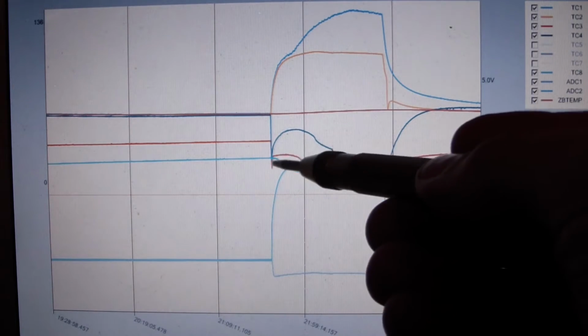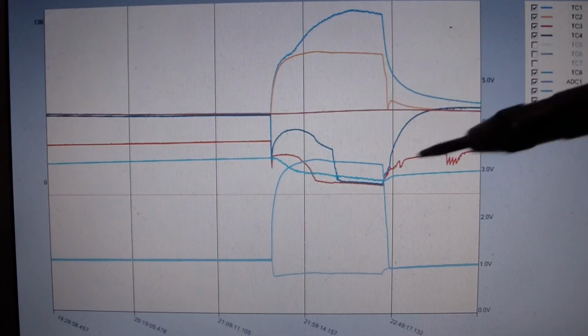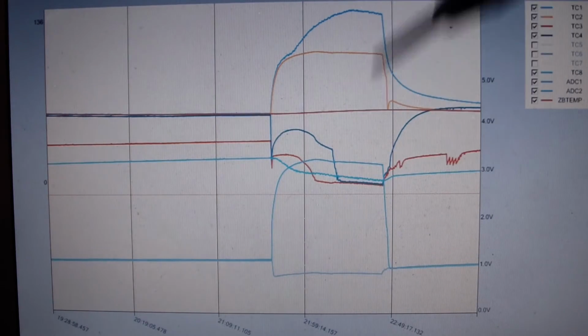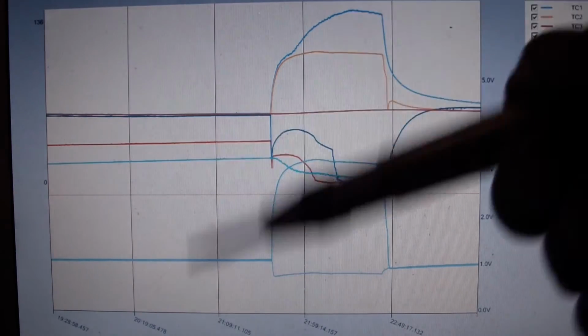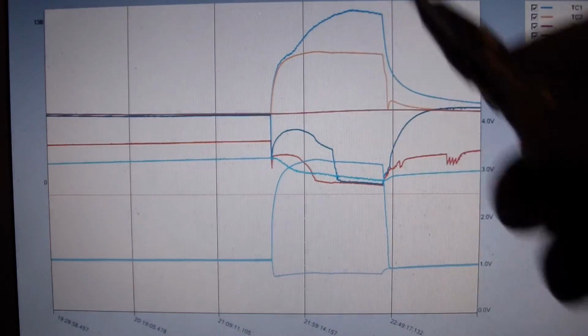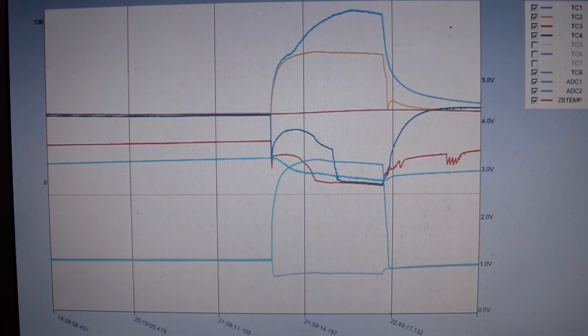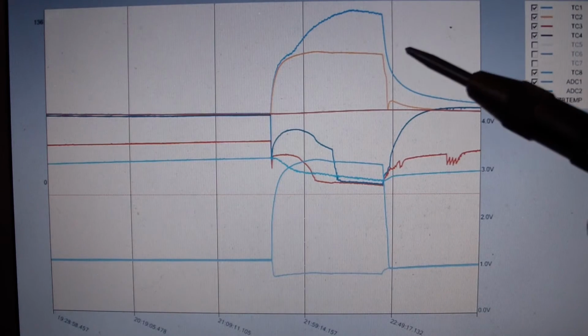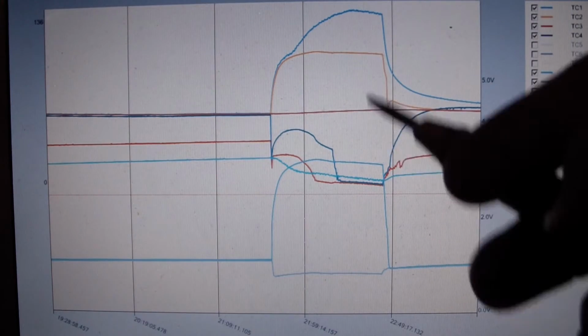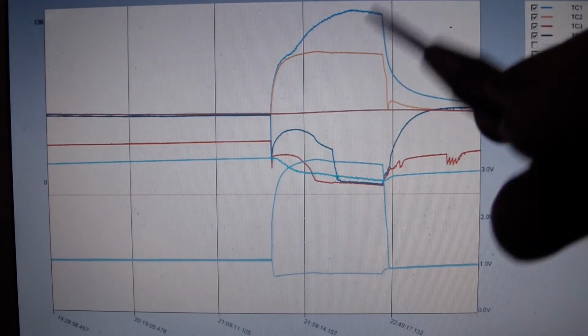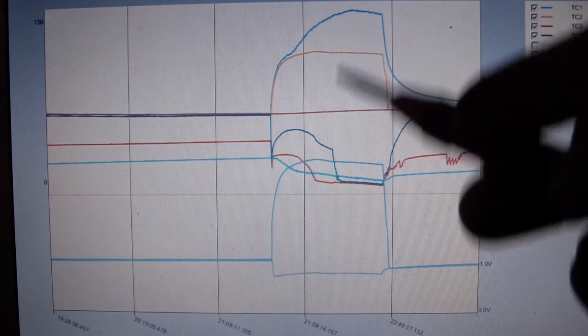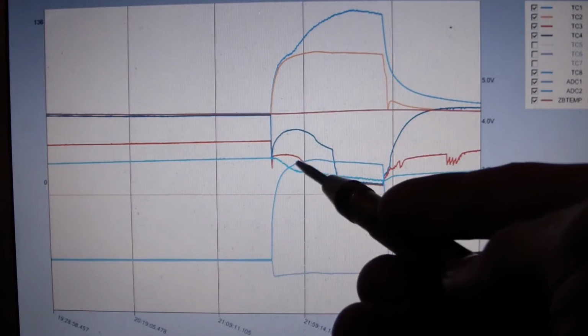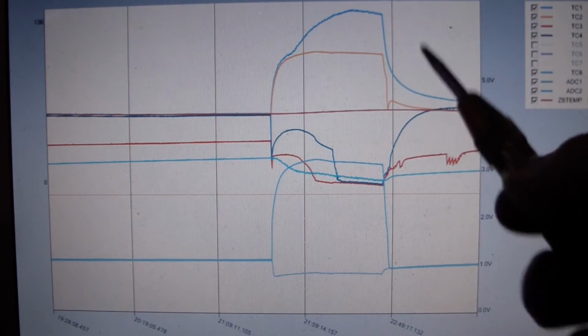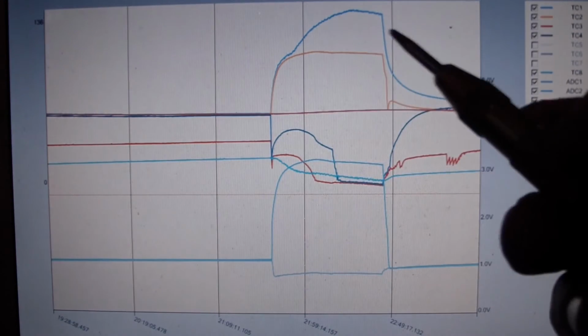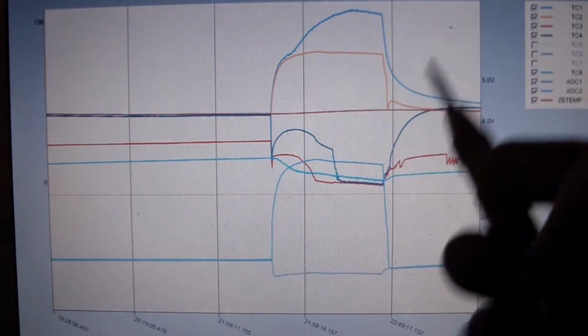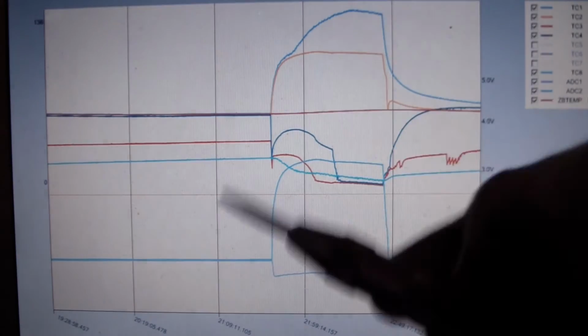whenever that suction superheat is so high, we end up with a rarefied, superheated gas going back to the compressor. And that's really bad for the volumetric efficiency of the compressor. For each intake stroke, suction stroke with the compressor, it draws in less massive gas, and then discharges less massive gas, as opposed to if it had a more saturated vapor, less superheated, denser vapor. So we have limited volumetric efficiency there and limited mass flow through the compressor. So even though the pressure is rising in the high side, it's not pushing a whole lot of mass, relatively speaking, into the high side to eventually get the temperature up and regain that liquid plug, by condensing that warm vapor.